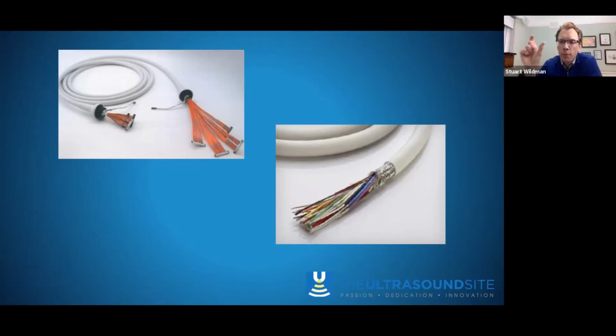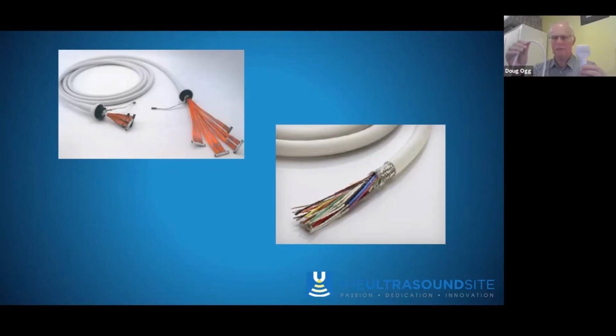And presumably the probe itself, the actual probe head, I don't know if you've got one there, you can just pop on the screen, Doug. But the probe itself and the cable all come as a unit, don't they? Yeah, a single unit when you purchase it. And the cable connector, you've got to remember that inside the connector that goes into the scanner, there has to be an equivalent number of connections, each of which must function perfectly to transfer those voltages back into the machine so that it can start to process them.